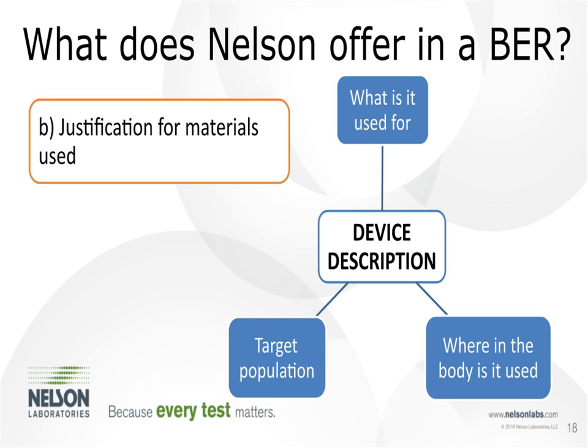The second section is Device Description — covering the target population, where it is used in the body, and its intended function. This begins the justification for materials used, because once we identify what the device is and state that these materials are common in this type of device, we've already given the specifics of where and how it's used.